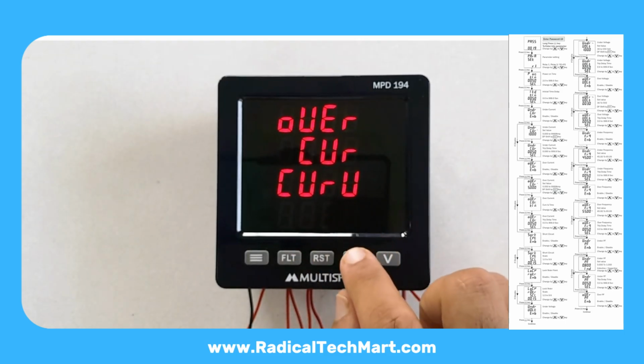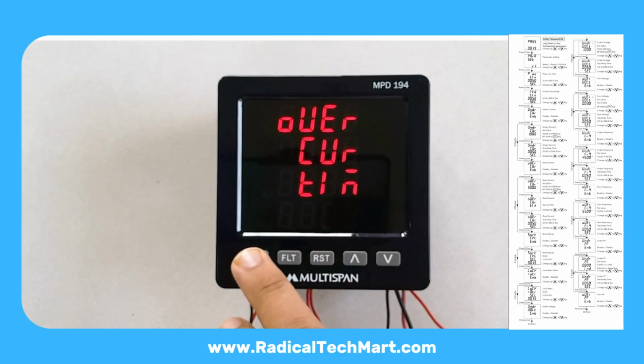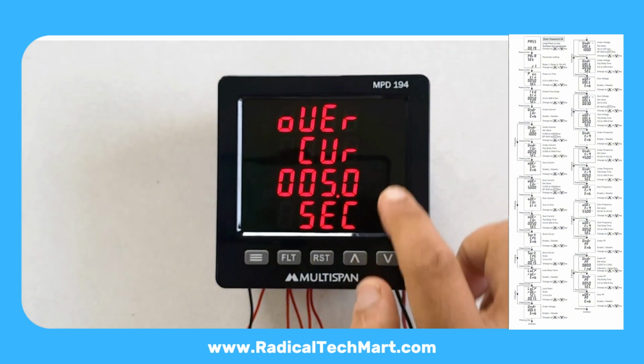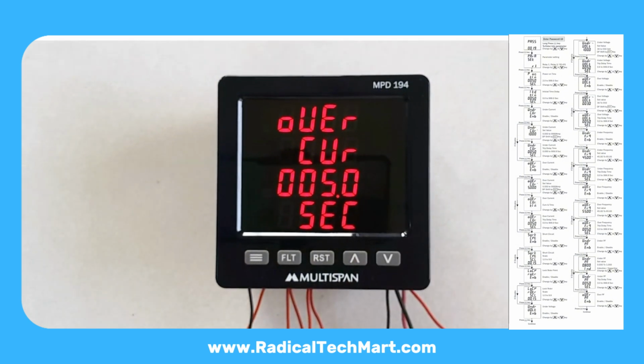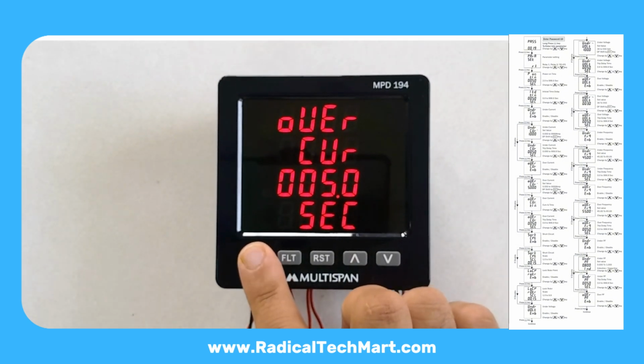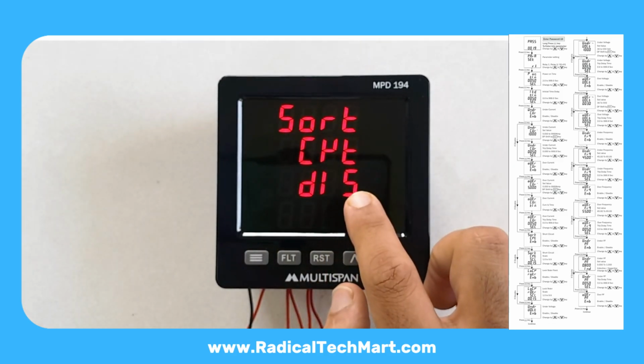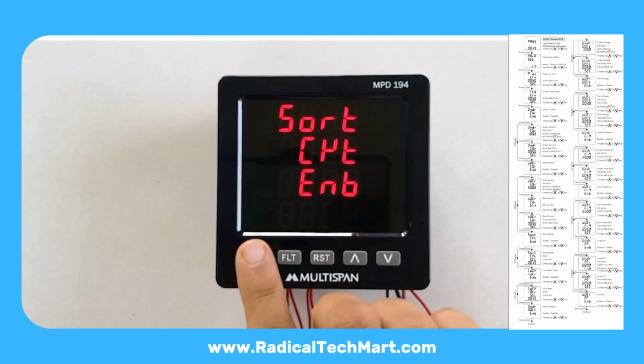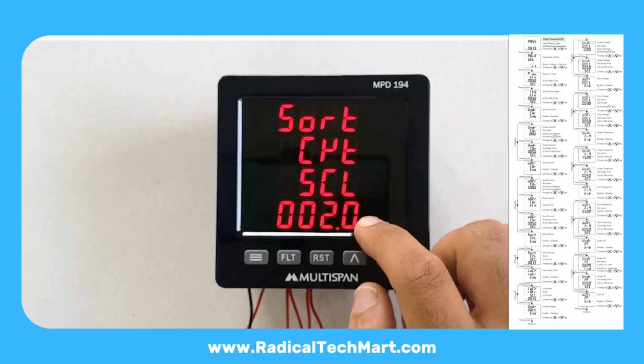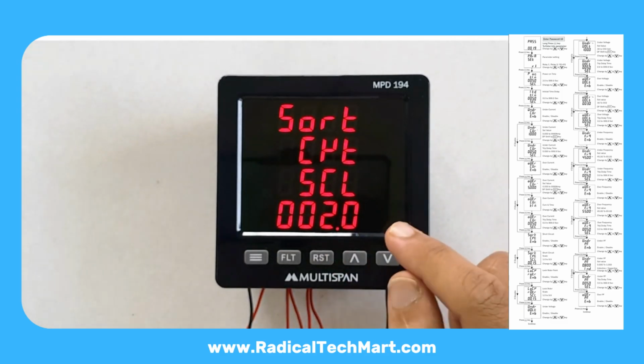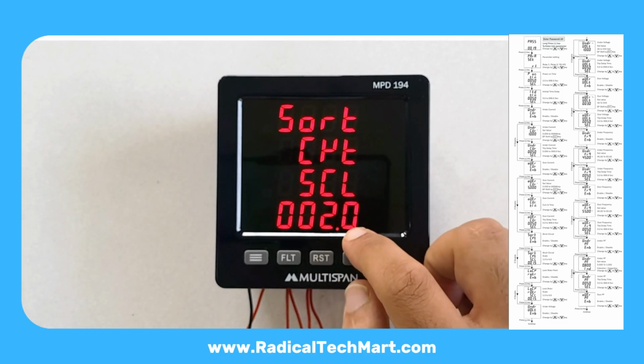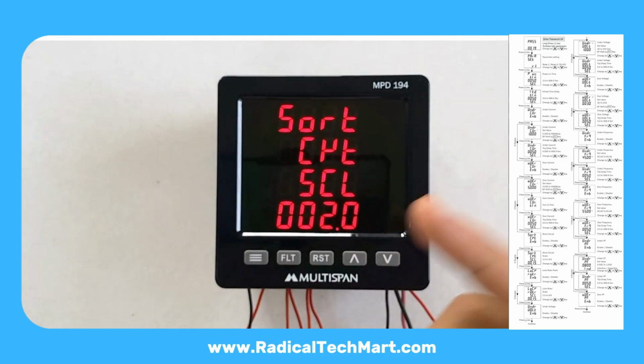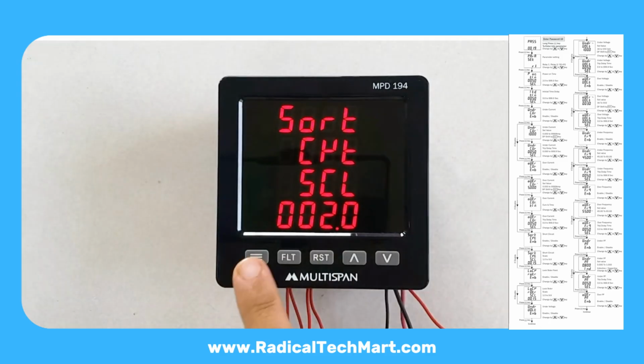Enable or disable short circuit. If enabled, you set a scale factor. Example: overcurrent is 10 amperes. The short circuit scale is 2. Then the short circuit threshold is equal to 10 times 2 equals 20 amperes. If current instantly goes above 20 amperes, the device trips immediately, ignoring the normal time delay.